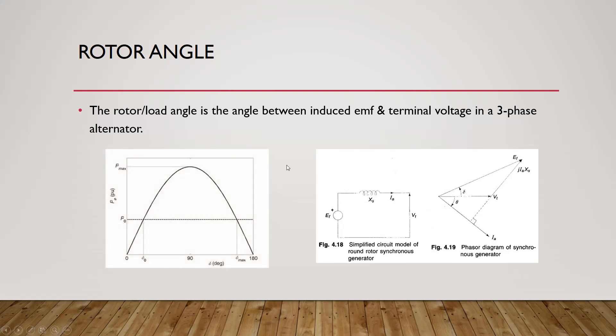Looking at the diagram showing the relation between the power output from our generator and the angle delta: this curve represents the relation between power and the load angle or rotor angle delta. This curve represents a non-salient, unregulated machine. A non-salient synchronous generator where 'unregulated' means the field current is constant and we are not controlling the field. We have different types of machines — non-salient and salient — and both can be regulated or unregulated.